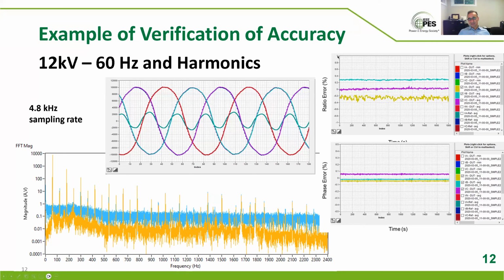But they put that in the field, looked at the accuracy, ratio error, and phase error over some time. It was supposed to be a plus minus 1% system, which after calibration it was and stayed, and plus minus half a degree. But we were also looking at its harmonic performance, which is what the people who built the digitization system tried to compensate for. Again, resistive dividers are not as good with that.